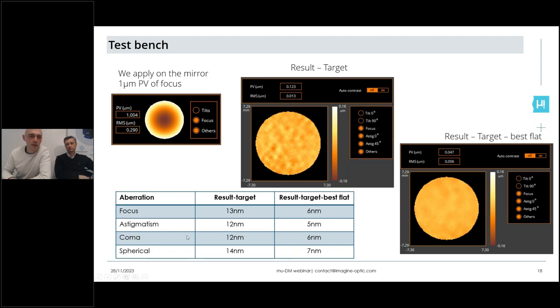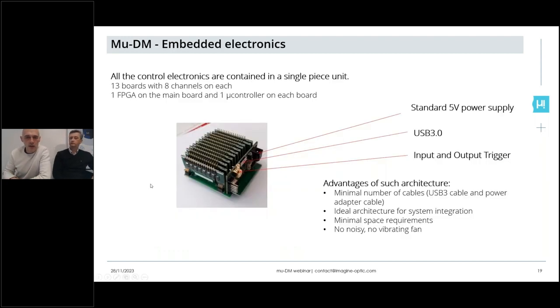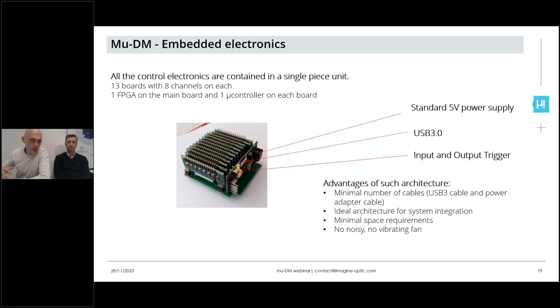In terms of integration, all the electronics are embedded inside the device — including the boards that drive the coils of the deformable mirror. Physically, there is a trigger-in and trigger-out connector, a USB connector that drives the whole device, and just a standard 5-volt power supply. The advantages are: no extra cables, no fans, no noise — making it really ideal for good integration as a module or even a complete system.